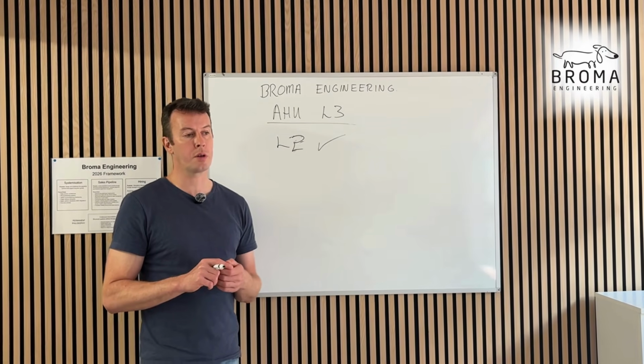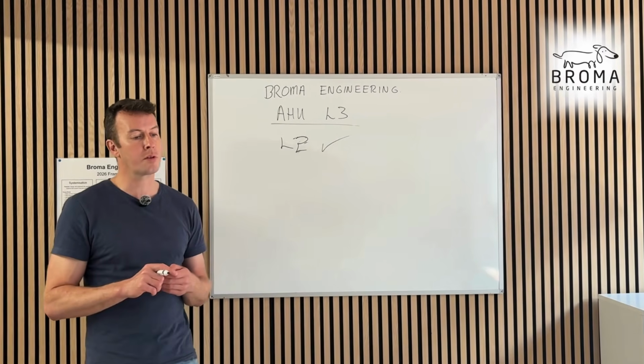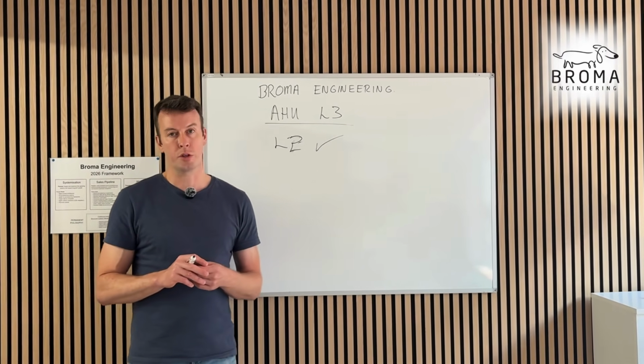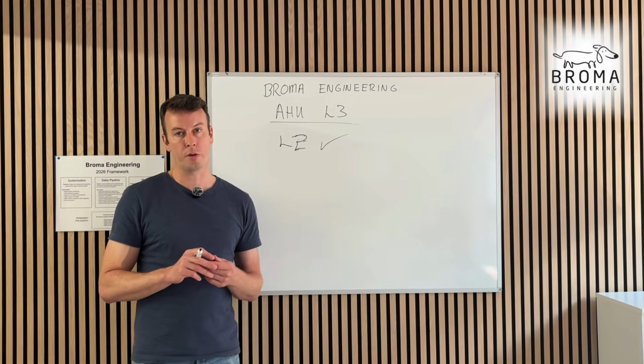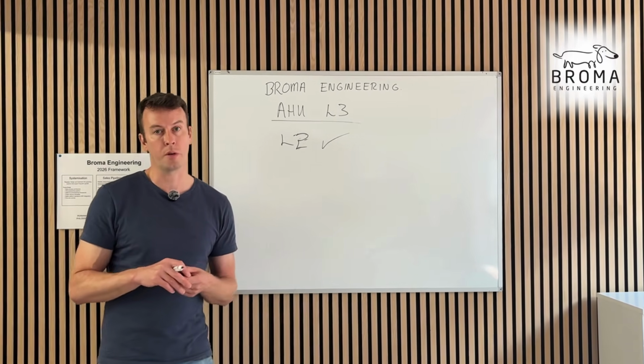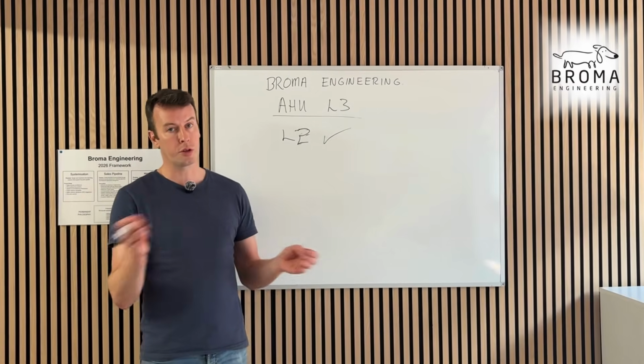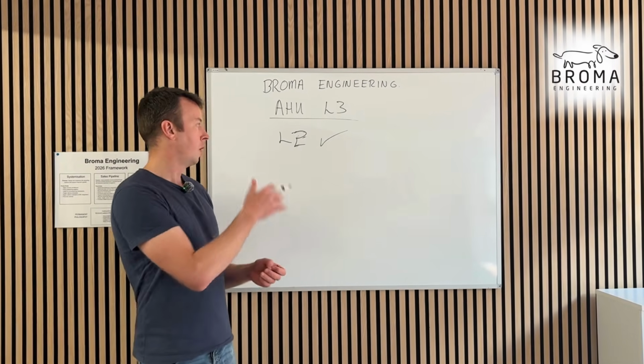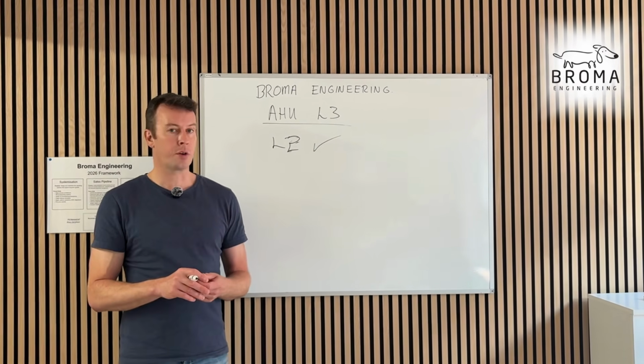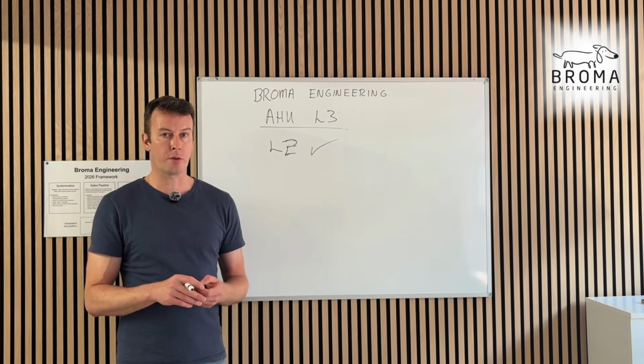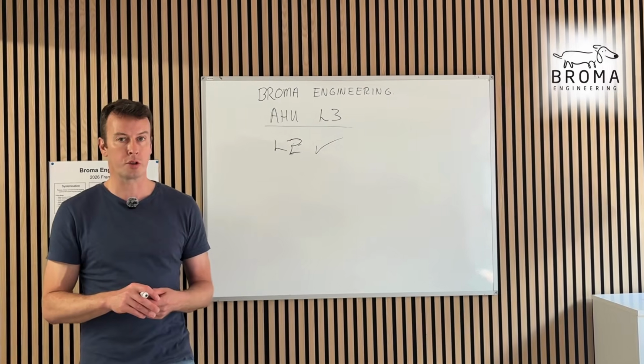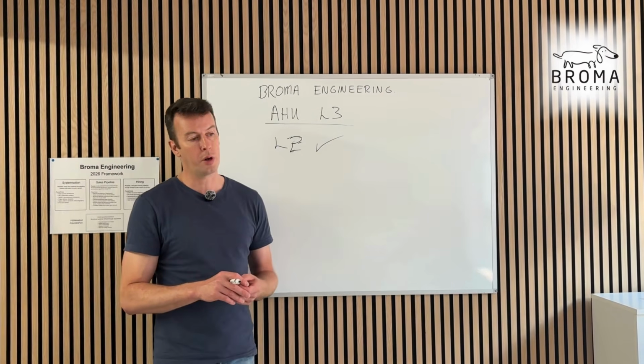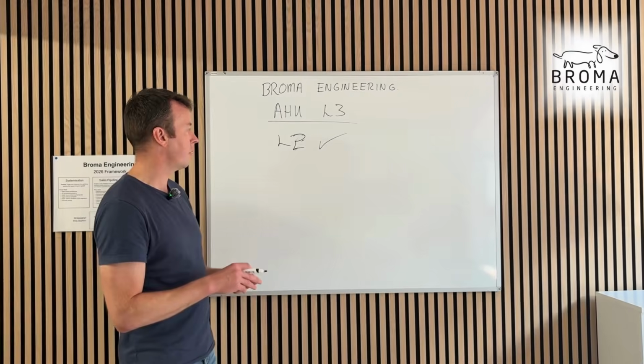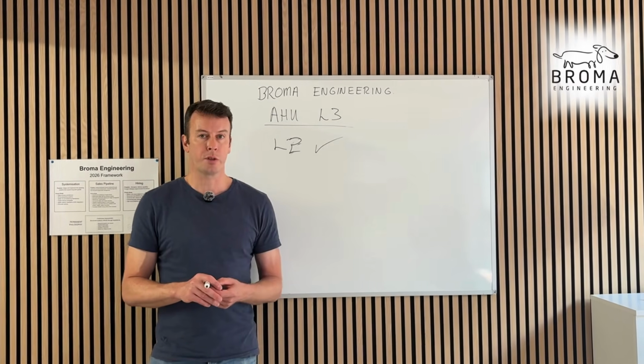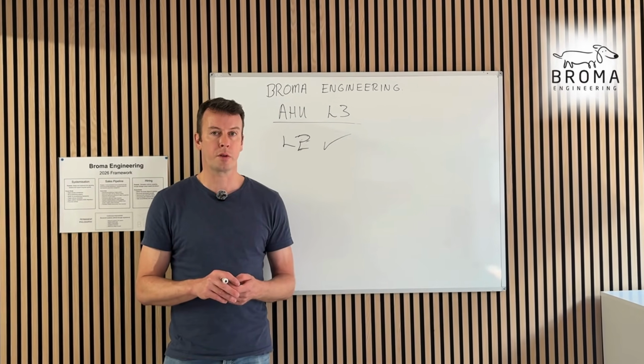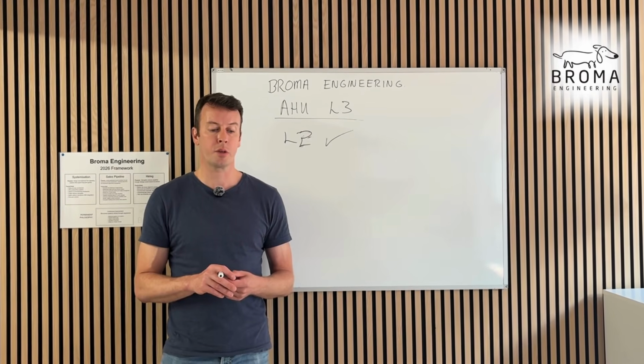Usually the vendor on a data center. If it was an oil and gas plant or pharma, you might have a commissioning team doing all of level 3, all of level 4, and all of level 5, what we call, as per ASHRAE. But that might just be the commissioning scope, handed over like oil and gas - you hand over after construction, and then a huge commissioning team does all the commissioning. But on data centers, it's the GC that does level 3. So level 3 is what generally people think of as commissioning.